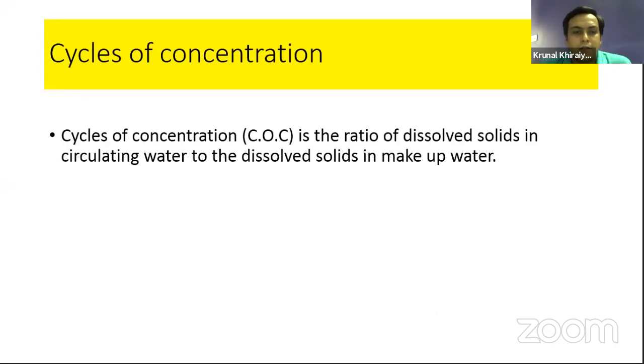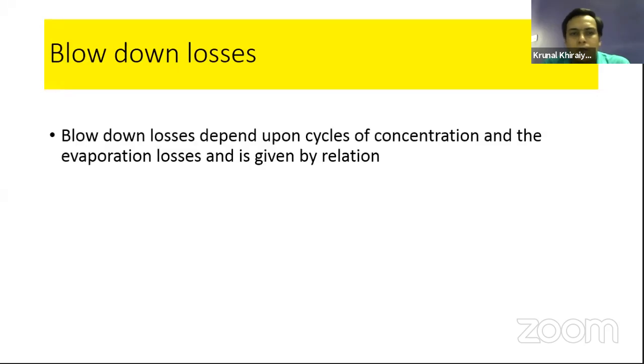Cycle of concentrations. The next important parameter is cycle of concentration. Cycle of concentrations, generally represented by COC, is the ratio of dissolved solids in the circulating water to the dissolved solids in the makeup water. This means you need to measure the TDS of the makeup water, the fresh or raw water, and of the circulating water. As we know, after circulating the same water for some time, the TDS concentration increases, and we need to blow down some of the water from the basin. So whatever water we treat is blow down from the basin of the cooling tower.